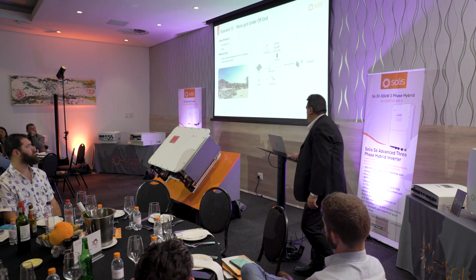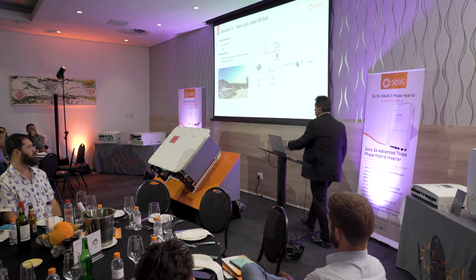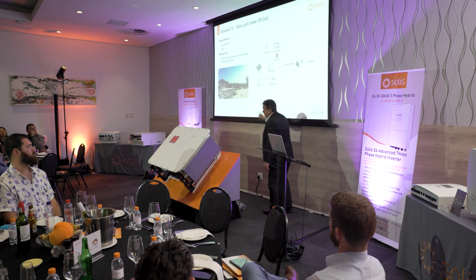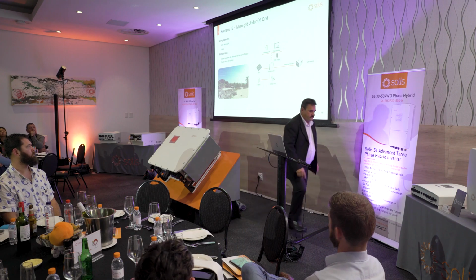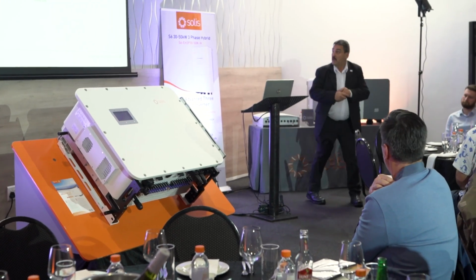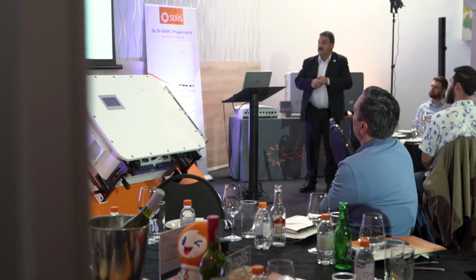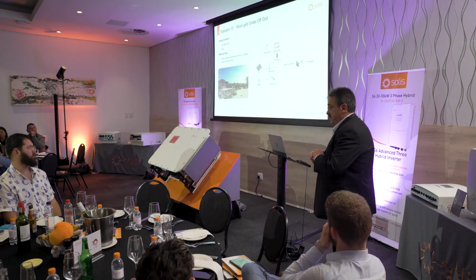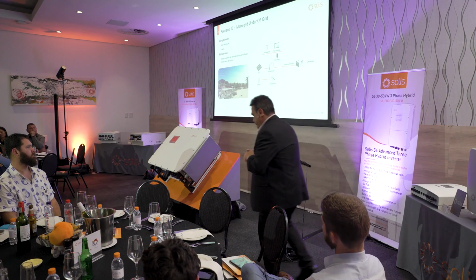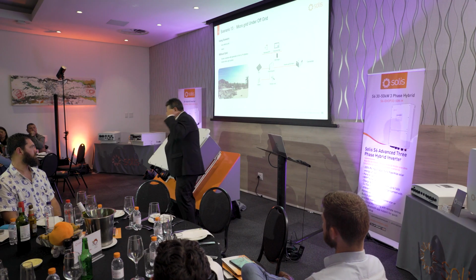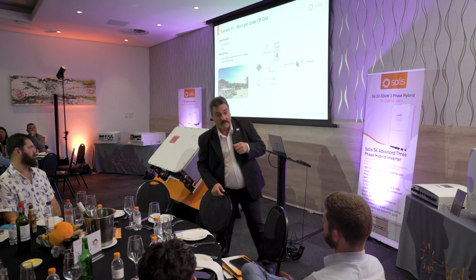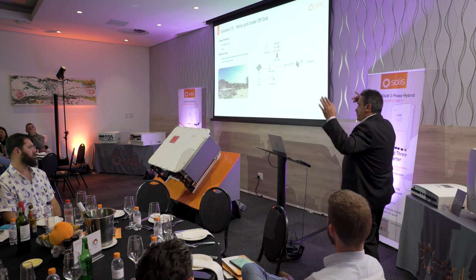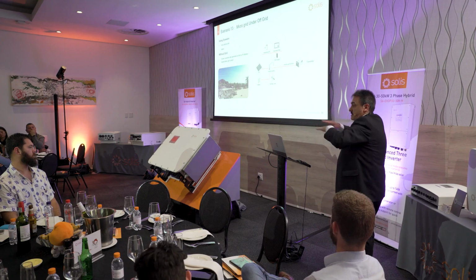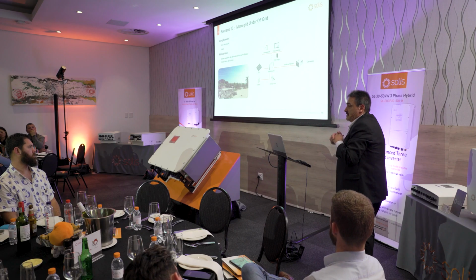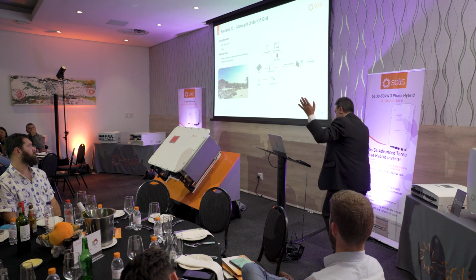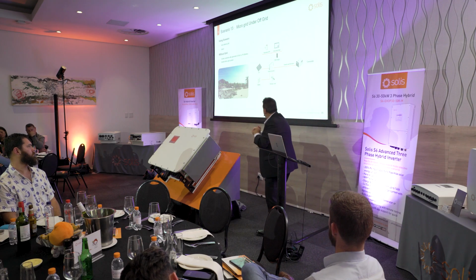So microgrid on the off-grid, so you also have the option of running the whole system completely off-grid, and then the generator on the grid side port, okay, as a mini grid. These are standard throughout all the products, basically. The only thing is that sometimes this machine doesn't know when a generator is on. Okay, because as far as the inverter is concerned, it sees power from the grid, regardless of the source. Right? And the inverter regards the grid as infinite power. It just can take as much as it wants.